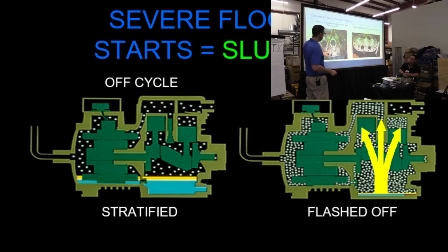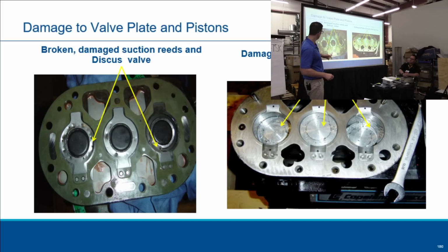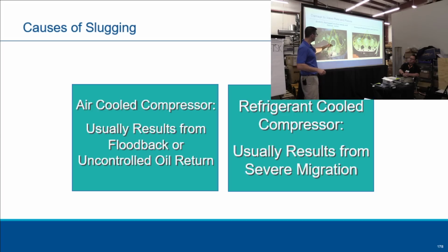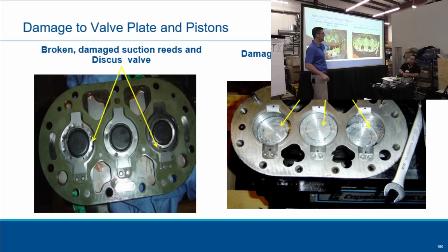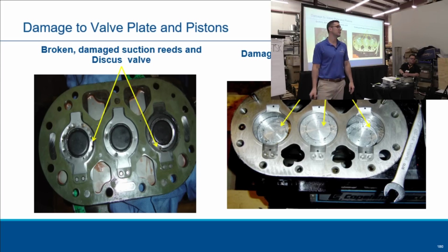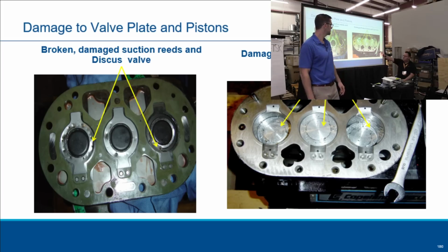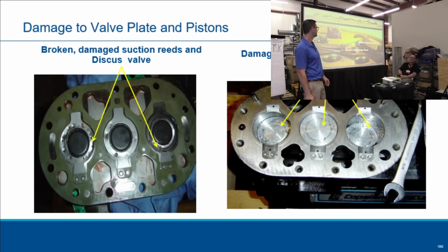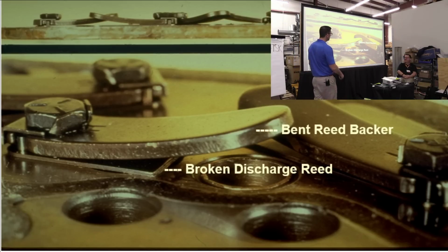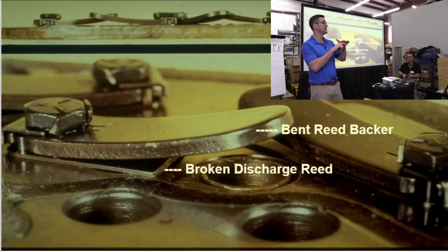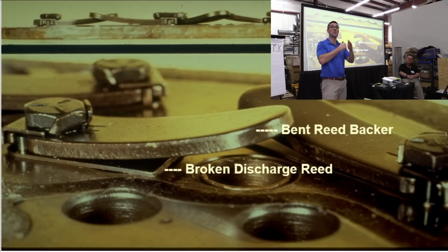So as you can see here, if we pull off the head on one of these today and flip it over, we see little dents in here, or a broken discharge valve. That's caused by liquid refrigerant getting up in there. We found a wrench in this one. Oh yeah. Haven't had a wrench before, is that what you're saying? Yeah. So from a slug you can see this, right? A broken discharge reed or broken discharge puck, the disc. That refrigerant gets in there, boom, breaks it.